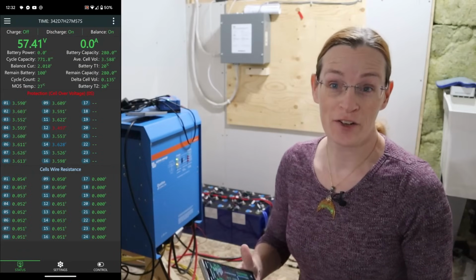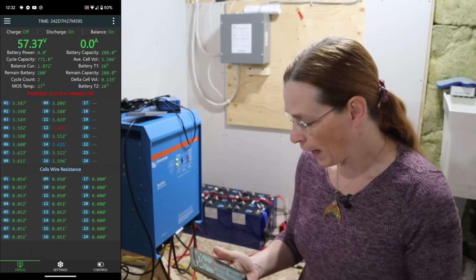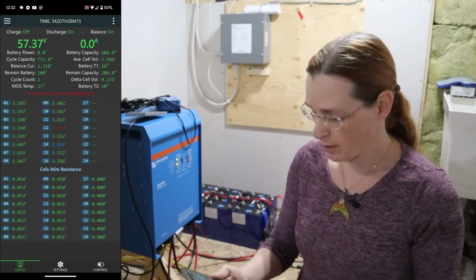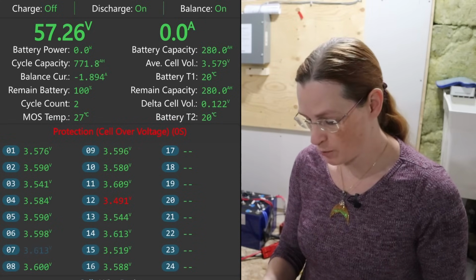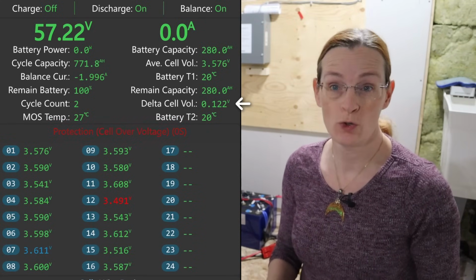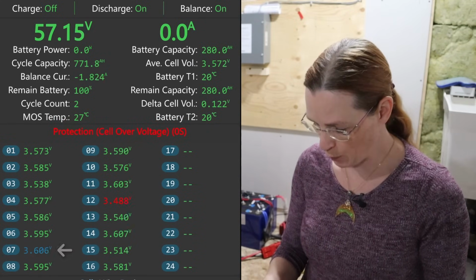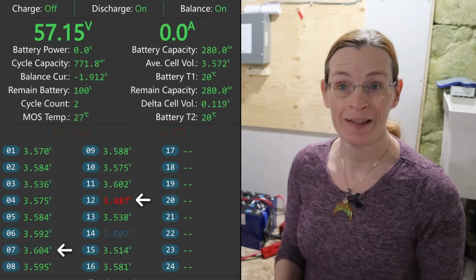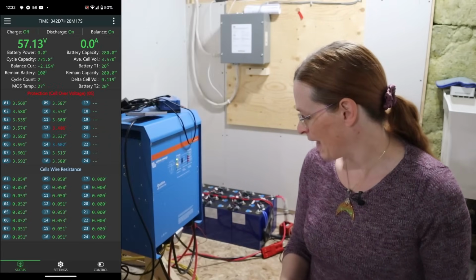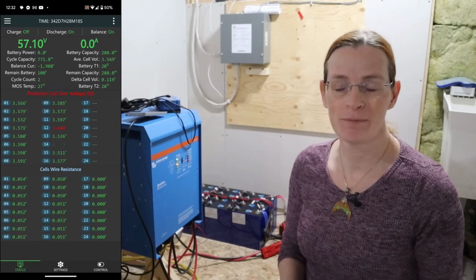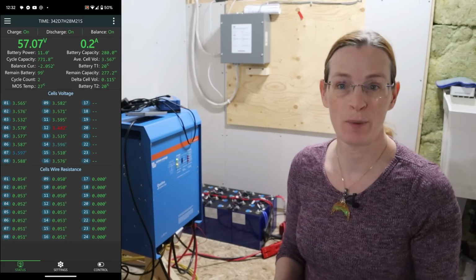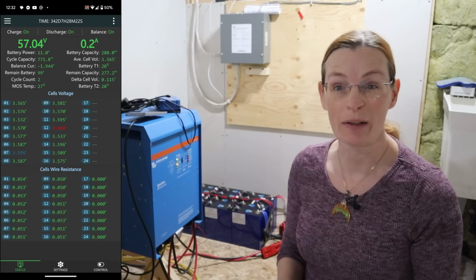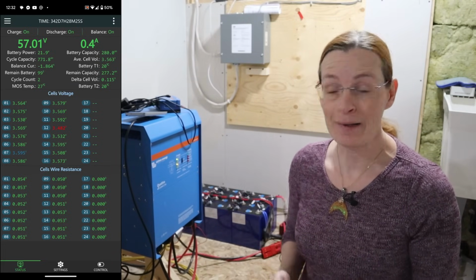So it is another day, and the battery is fully charged-ish. It's gone into overcell protection, which I expected, with a 0.122 deviation. 3.6 versus 3.4. So I'm kind of wondering, by stopping the charge and balancing at 3.55, if I didn't actually balance it. So I'm going to leave it.